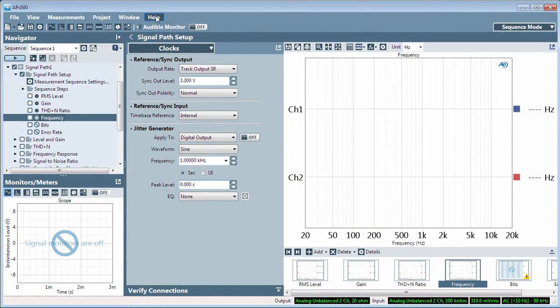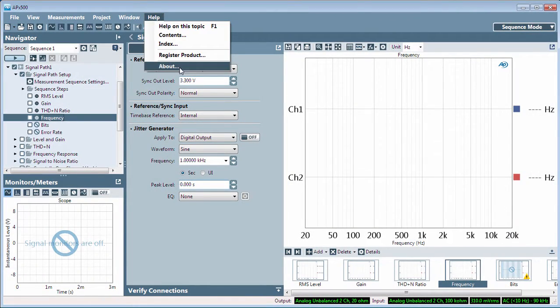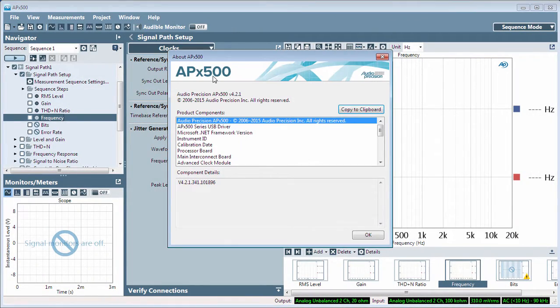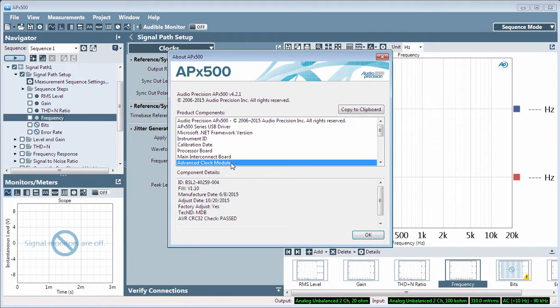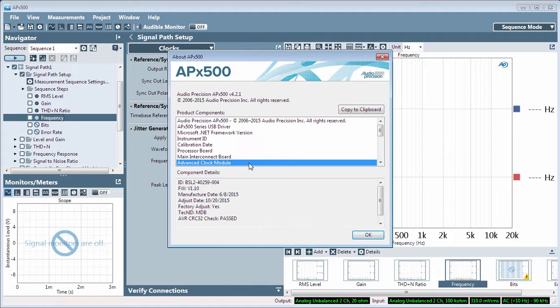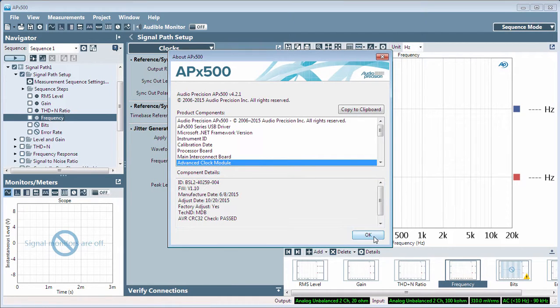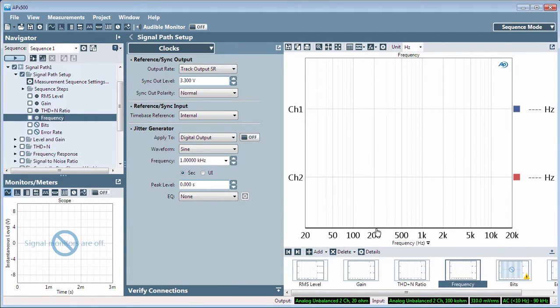With an APX analyzer attached, the Clocks menu is only available if the instrument is fitted with the advanced master clock hardware, which is standard in an APX555 and an option for the APX525 and 585 series instruments. You can always view the Clocks menu by launching APX500 without hardware in demo mode.